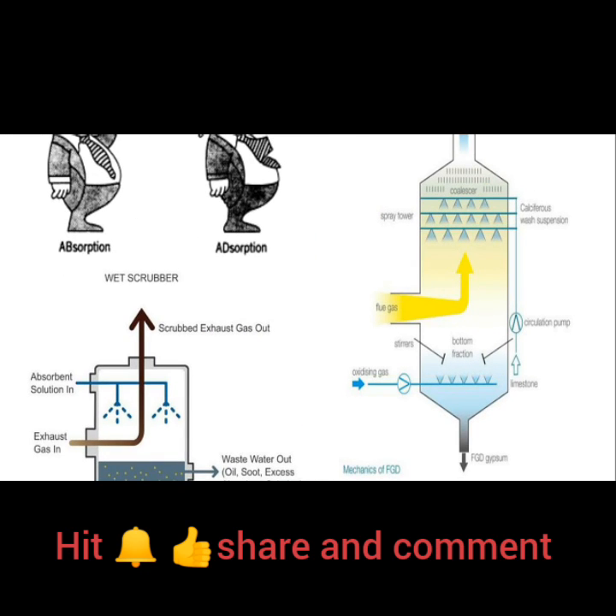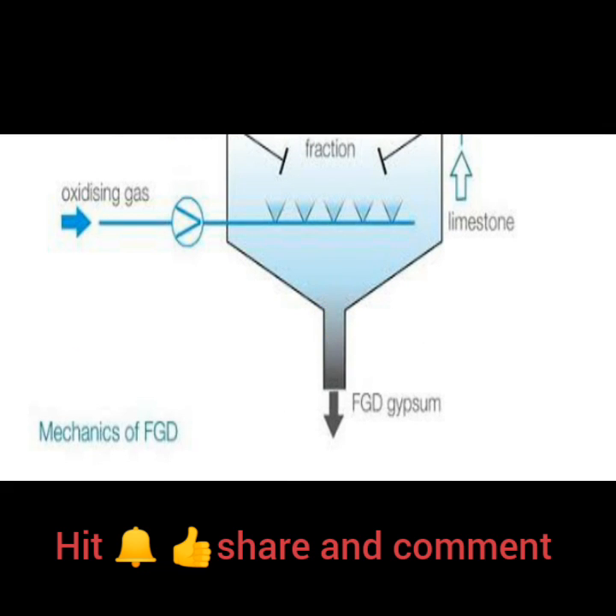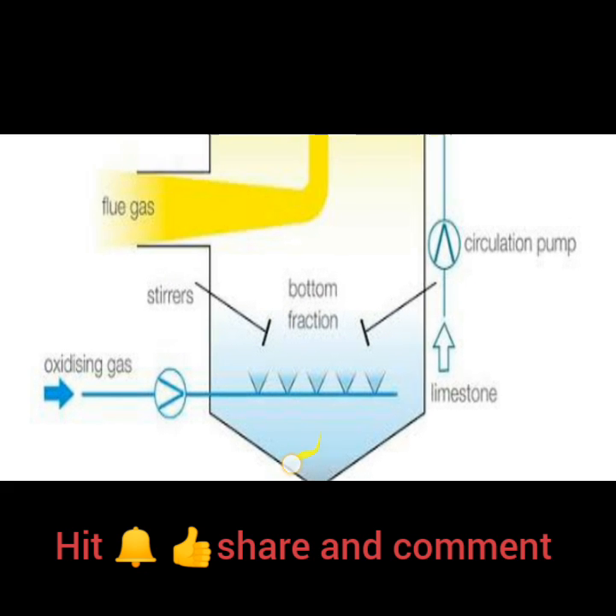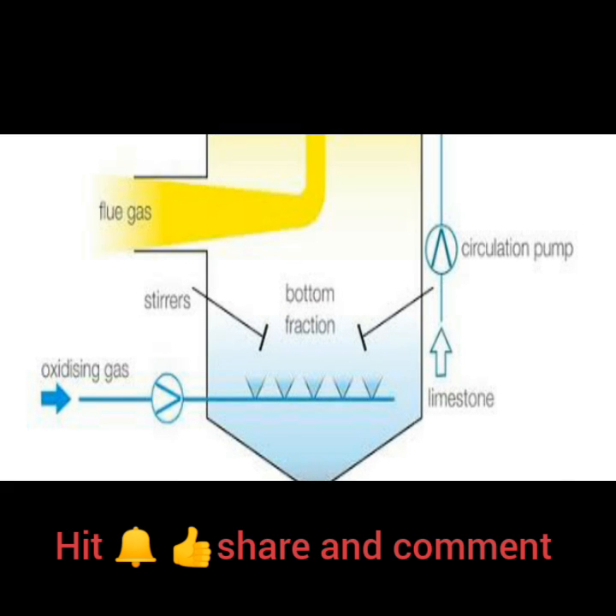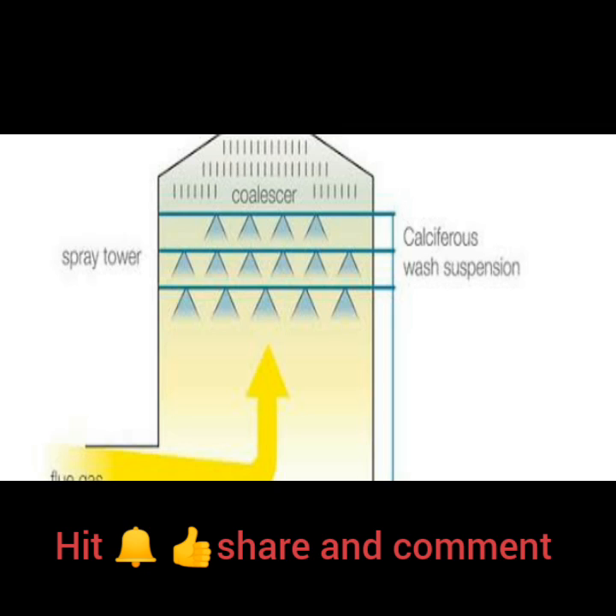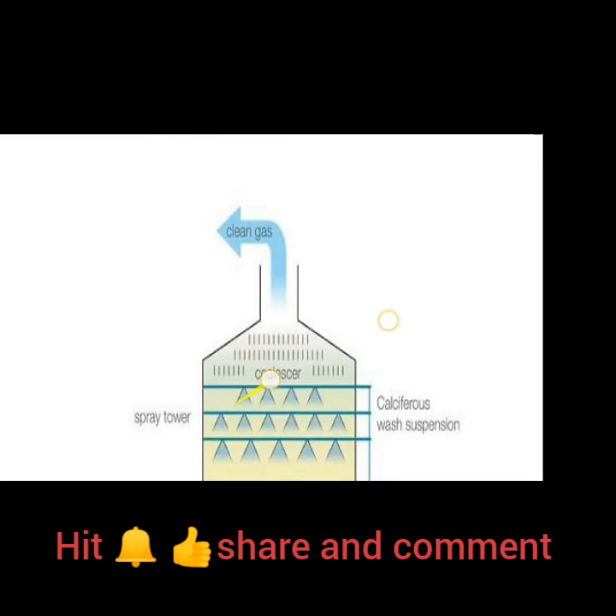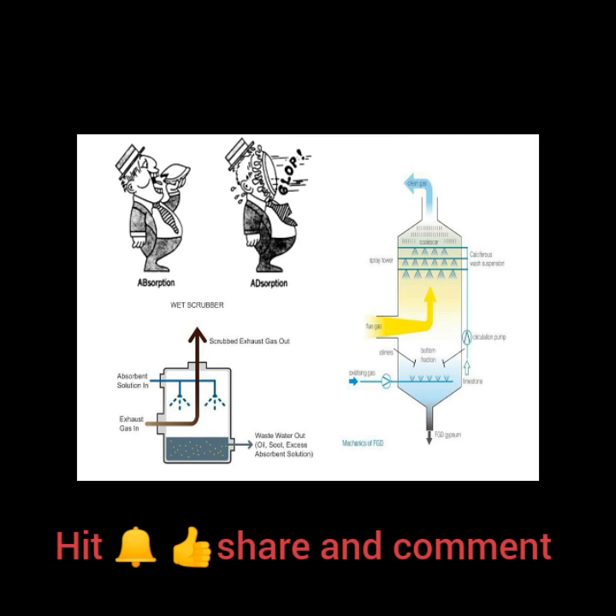Regarding the FGD mechanism: the diagram shows gypsum at the bottom, oxidizing gas and limestone going upward, a storage area with a circulation pump, and flue gas inlet at the top. We have a spray tower, calcareous wash suspension, a coalescer, and clean gas outlet. This is how FGD works.